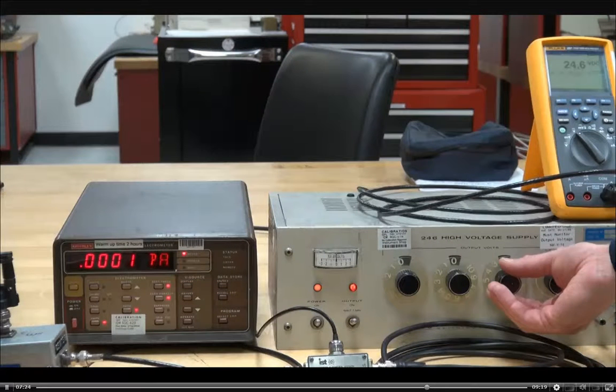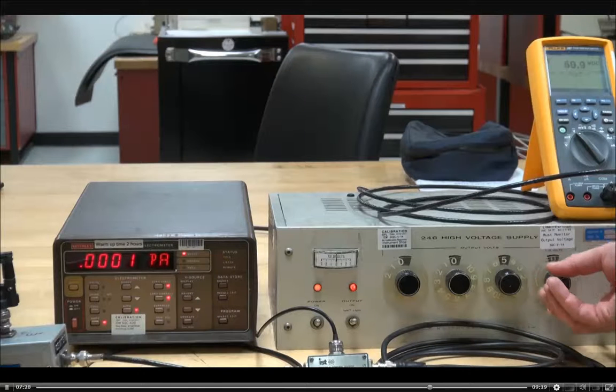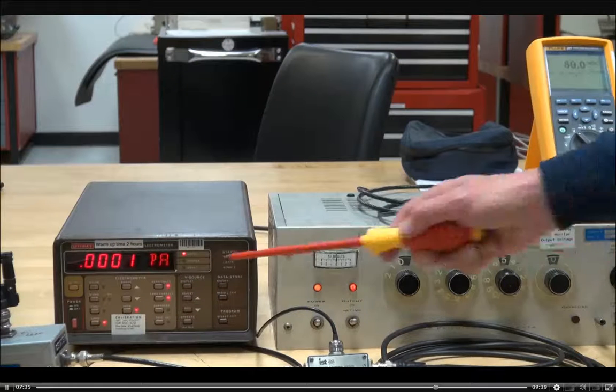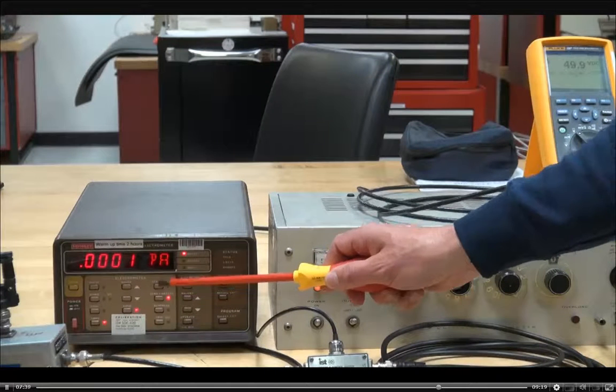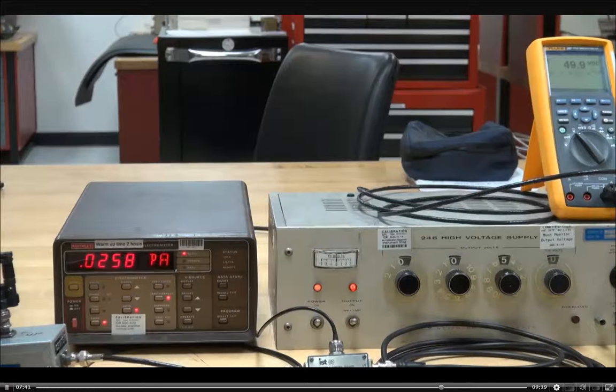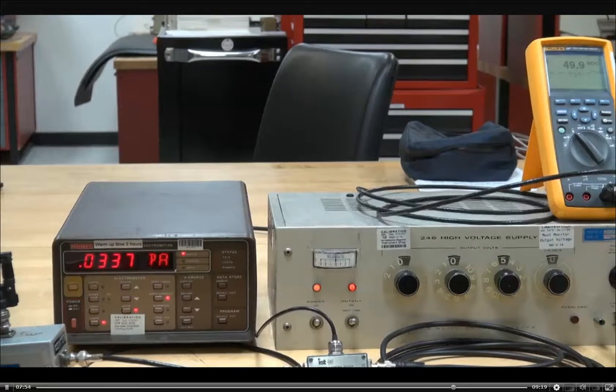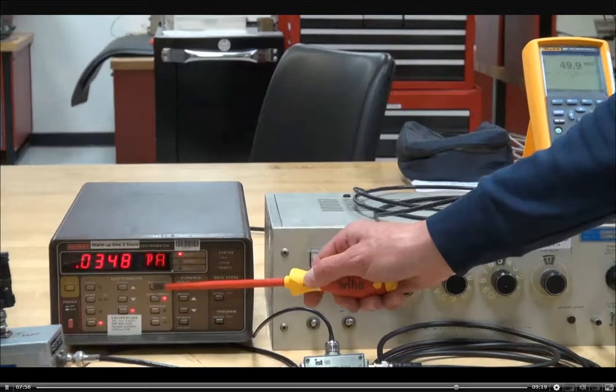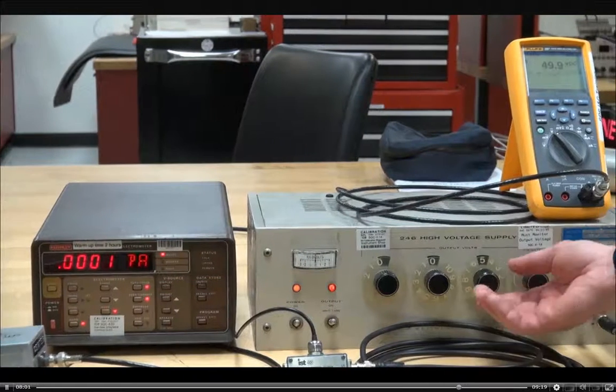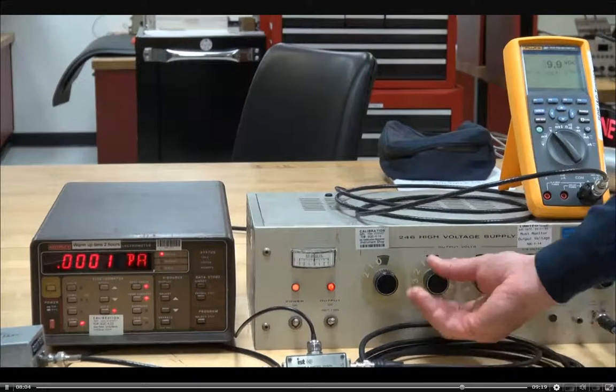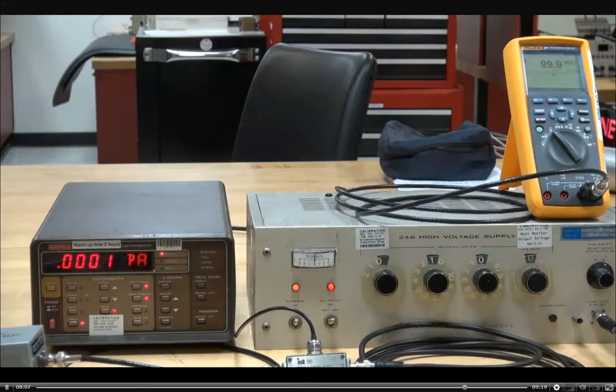The next setting would be 50 volts. We have 50 volts. You would wait your 1 minute for everything to stabilize. And again, 1 minute later, you can see it's still stabilizing a little bit. 0.03 picoamps. Zero check back on. Next reading is 100 volts. And so on. Okay. Good? Marvelous. Okay.